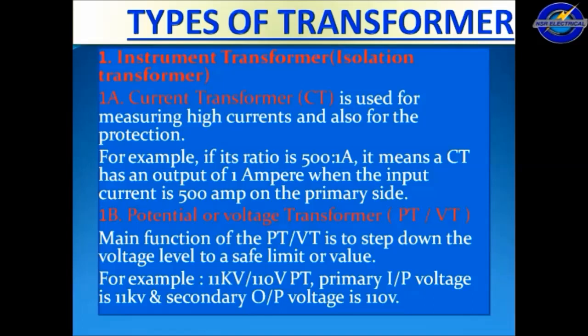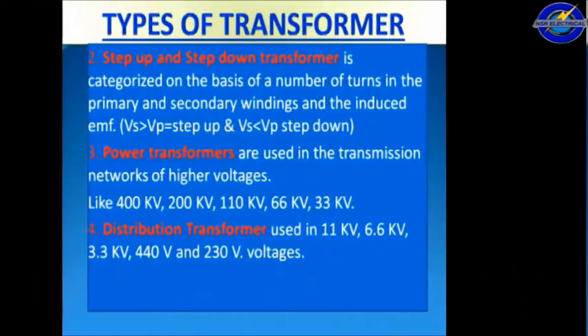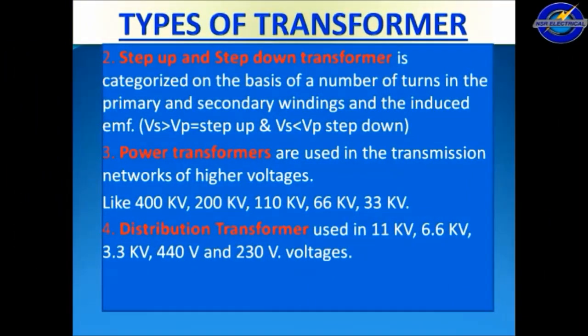Potential transformer (PT) or voltage transformer (VT): the main function of a PT is to step down the voltage level to a safe limit or value. For example, if we have to measure 11 kV, it is critical to measure directly, so the PT steps down 11 kV to 110 volts. The primary of the PT is 11 kV and the secondary output voltage is 110 volts.